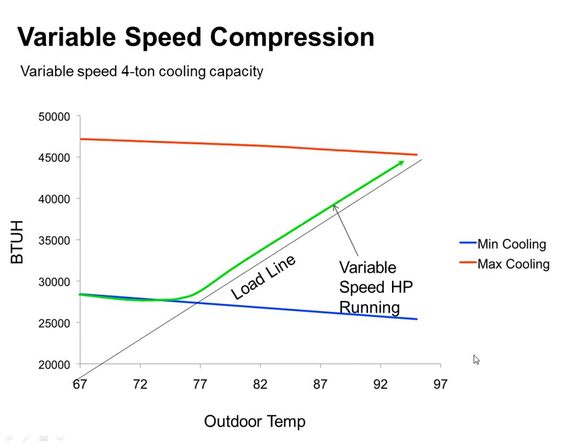Some of the things you'll note: the outdoor condenser fan has to be variable speed also. We can't just change the compressor speed and not change the airflows and expect things to work. So both the indoor and the outdoor fan have to be variable speed. I'm probably going to have an inverter that drives the compressor. That's the way almost everybody does it. There are other ways to have variable capacity compressors, but an inverter-driven one is the majority of them. Sometimes that inverter will also drive the condenser fan motor. Sometimes the condenser fan motor will have its own controller.